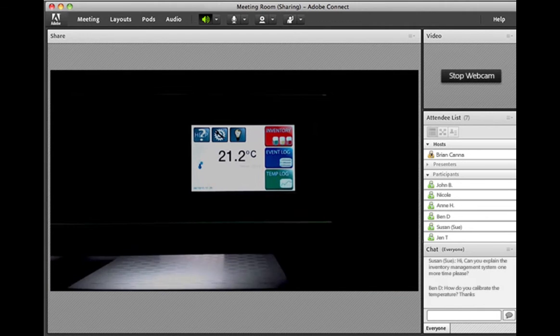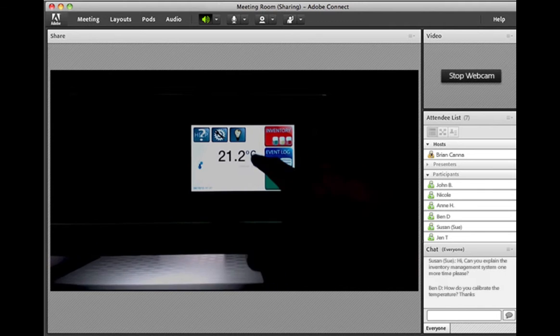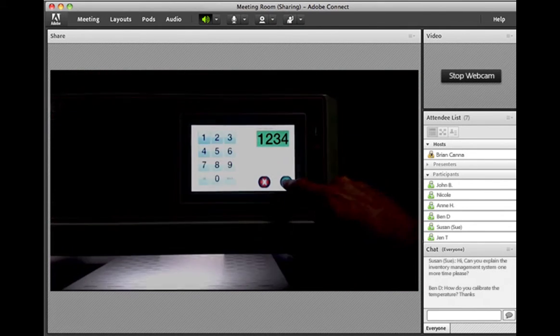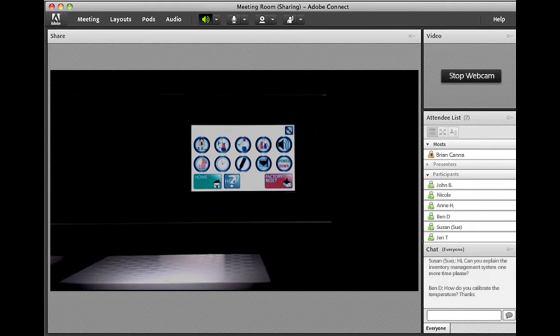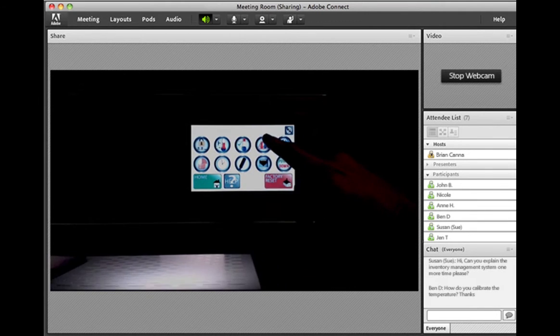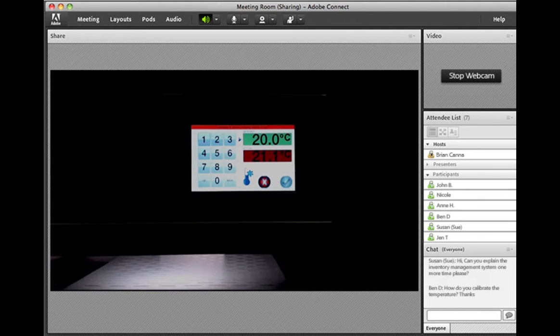So it looks like we have another question about calibrating the temperature. We will go into the settings menu to do that, and we'll enter our passcode, our default passcode, and to check the temperature or calibrate the temperature, you use this icon right here. So the way that you calibrate this unit is first you will calibrate the cold, and you will have your temperature measurement device in the unit, and you will enter the actual value. So right now it's trying to achieve a temperature of 20 degrees C. We would have a thermometer or measuring device, an RTD, inside the unit, and then we would just enter our actual value for our calibrated device right there.